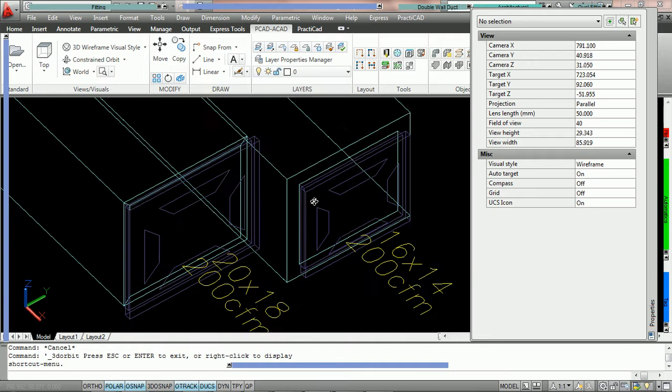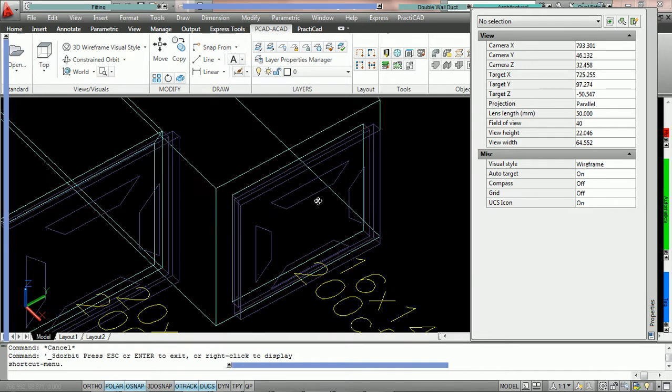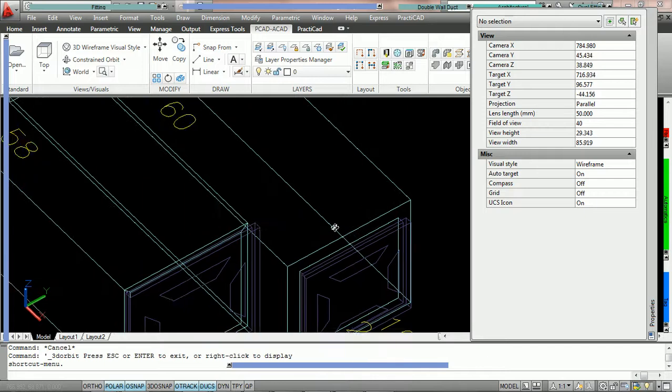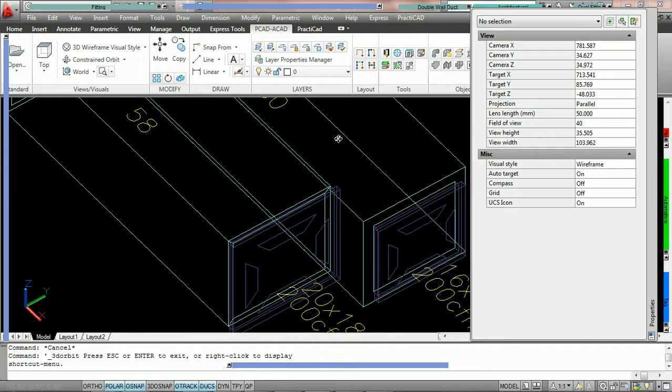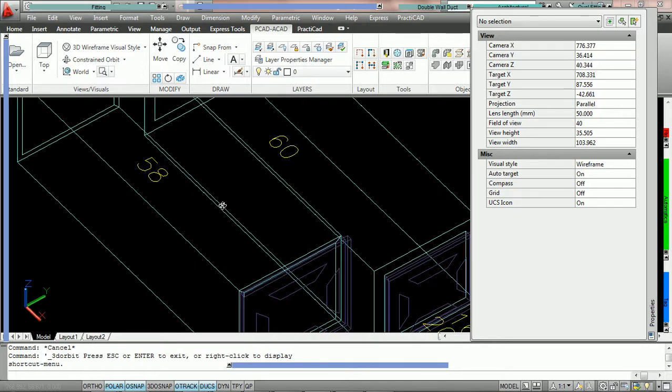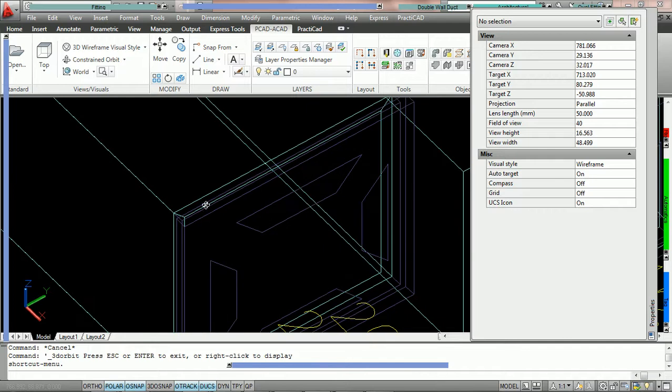However, with the connector flange parameter, when you snap a grill, it snaps the neck to the inside of the connector flange. Now this flange, regardless of how large or small you make the value, has no bearing on the length of the fitting. So you can see that this fitting here is 60 inches, the one with the PractiCAD connector on it. The one we did the 1-inch flange in, we made the connector size 1 inch. So we lost an inch on each side of the fitting to create this connector.